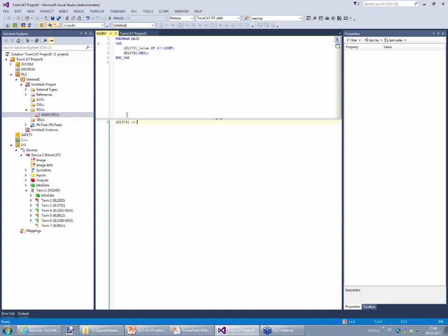I write it here, and so I can calculate now, Ctrl+C, Ctrl+V, and I have to calculate it with 7812500, and I have to multiply it with 10, because in my setup here I want to measure 10 volt now. This is what I give out from my process calibrator and what I have selected in the analog terminal, and this number I will explain later.